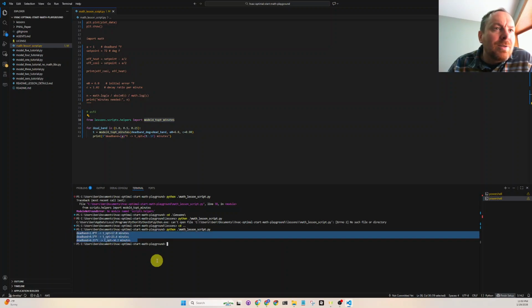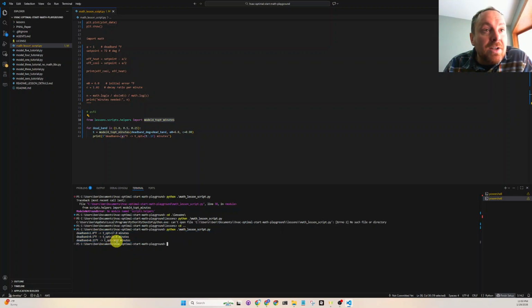So basically, it's just some simulated code that's saying the shorter the deadband, the more minutes that your control system probably has to run, which makes sense. That's why for energy use cases, I think that the wider the deadband, the less time you have to use mechanical cooling, electrical energy on fans or chillers or boilers to get to your set point. So if our deadband is really small, the HVAC system could take more minutes to achieve that temperature set point. Hopefully that makes sense.